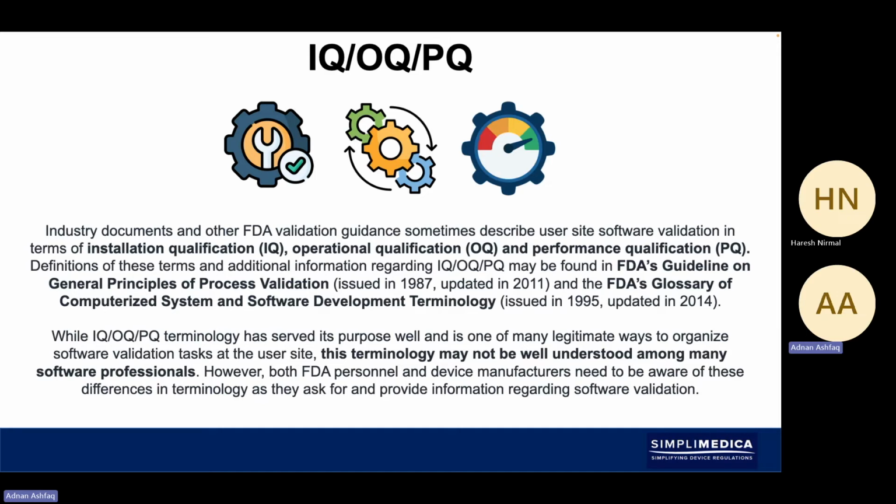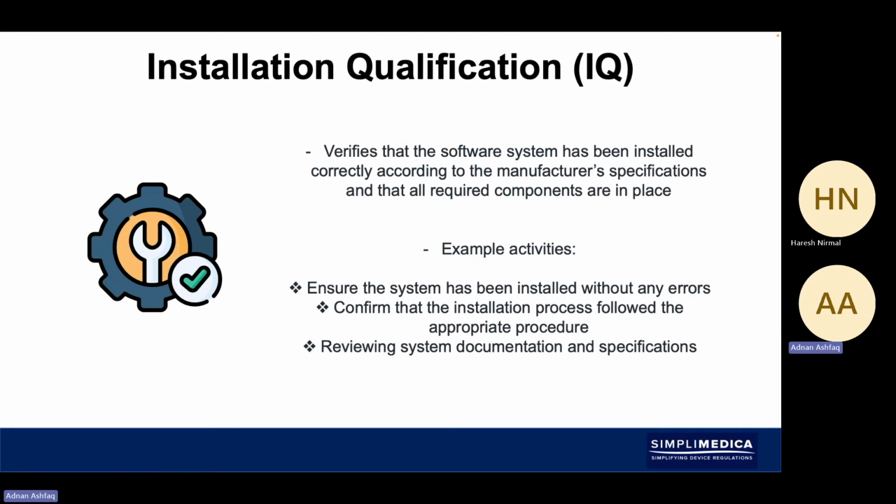The IQ is making sure that any required installation is done. That's where you verify that the software has been installed correctly according to the manufacturer's specifications and that all required components are in place. For example, the system is installed without errors, you confirm that the installation process follows an appropriate procedure, and then you review system documentation and specifications.